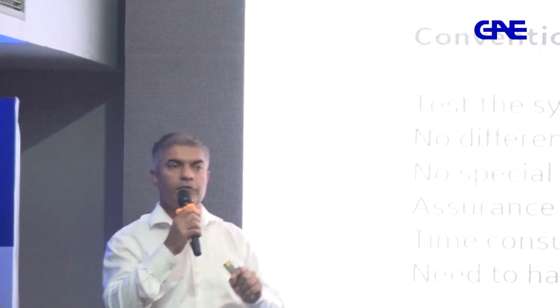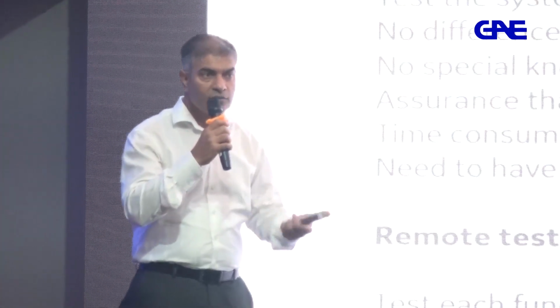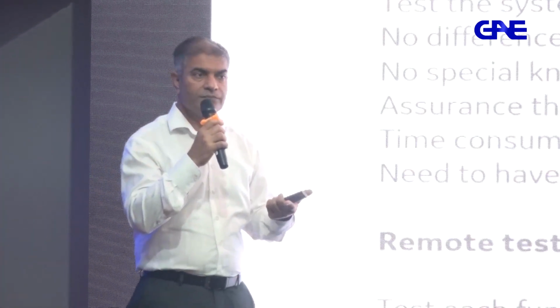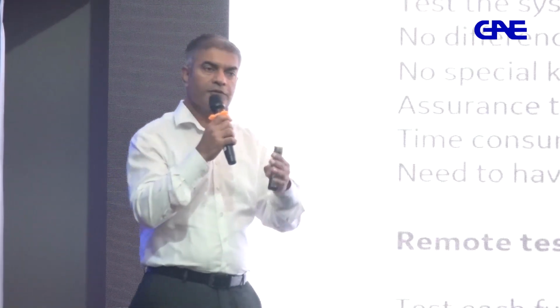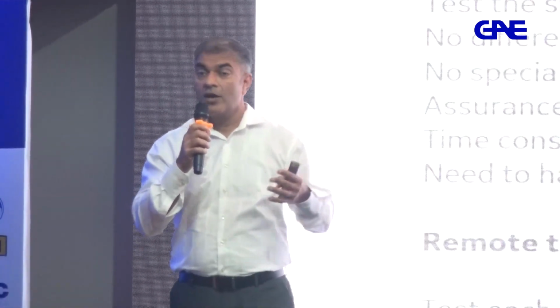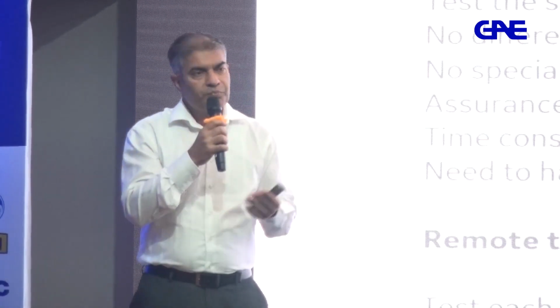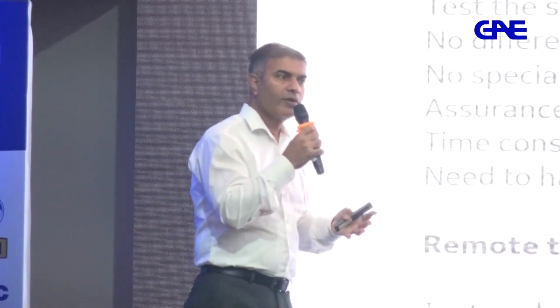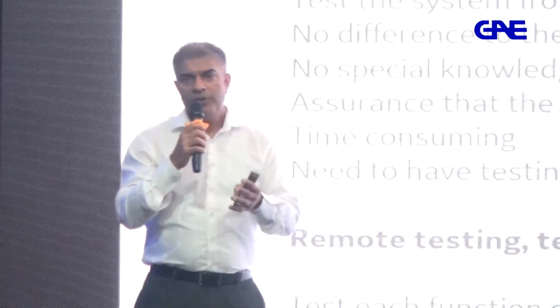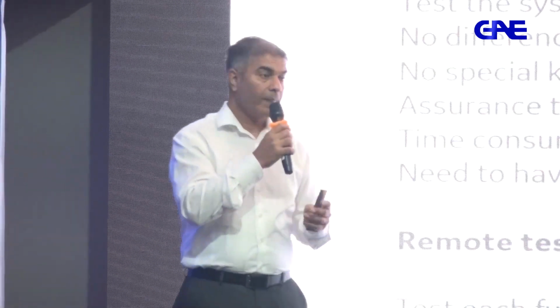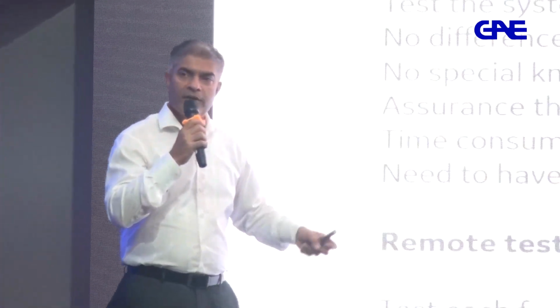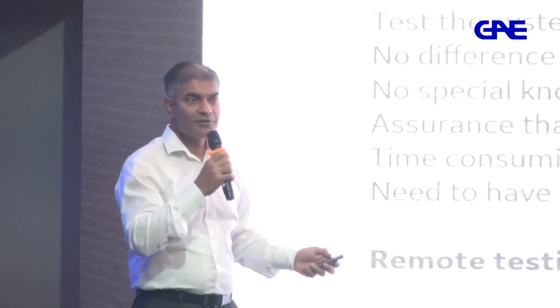In conventional substation, if you want to test, you have to take shutdown, right? You can't do it when the equipment is live, because the protection is still on. Of course, you can make a short circuit of CT, you can run your feeder, and you can disconnect all your wirings, but that's very complicated. I mean, the test links, you can open the test links and inject current and voltage, but think about bus bar protection and all, because it becomes very complicated, right? If your device is involved in a circuit breaker fail, how many test links you will open, you need to be very careful. In digital substation, you can very easily accomplish all this task with test mode and simulation.